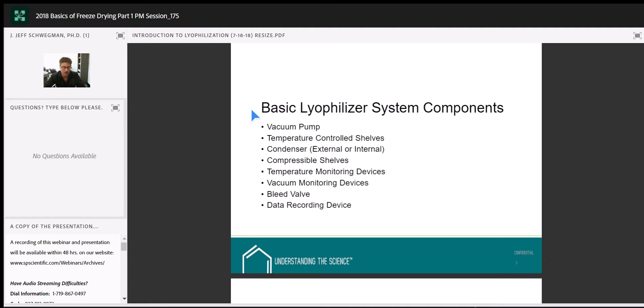We want to make sure we're doing this in the most efficient manner. Temperature-controlled shelves — this is not an absolute necessity. There are people doing freeze-drying on non-temperature-controlled shelves, but generally for pharmaceuticals, diagnostics, and the tissue industry, we use shelves with thermal fluid that we can control and monitor the temperature of through a heat exchanger.